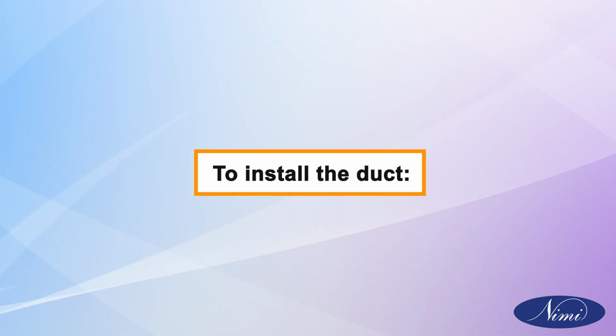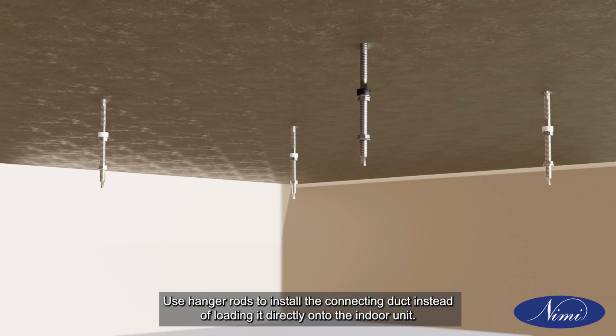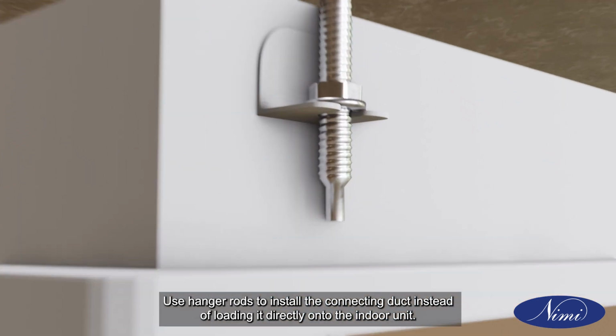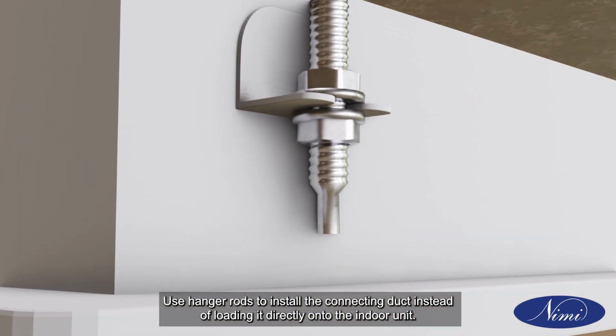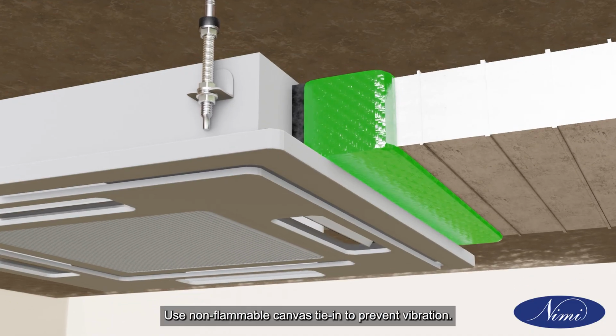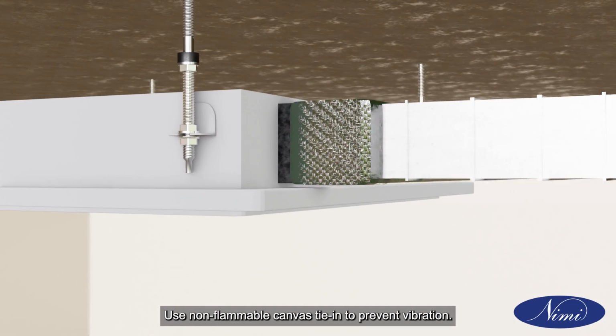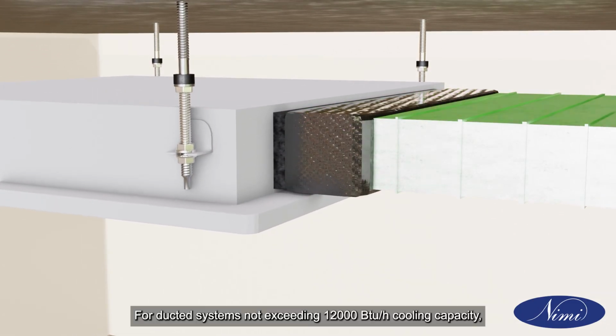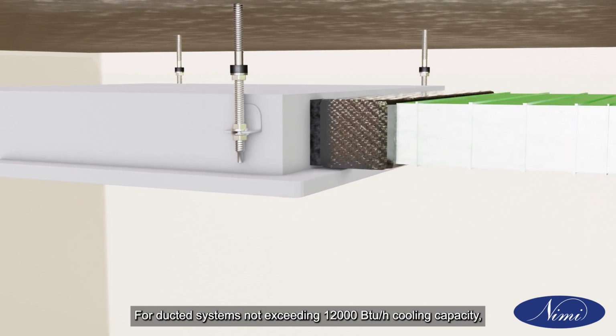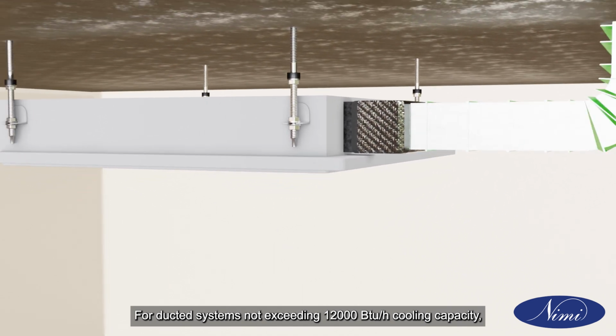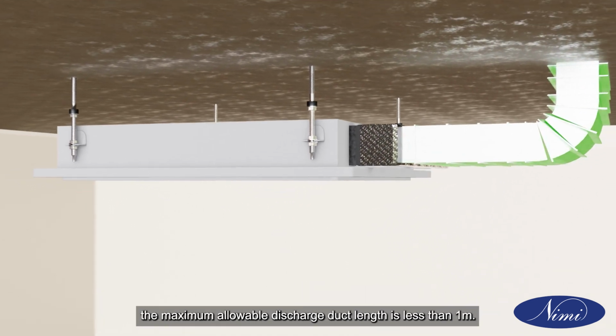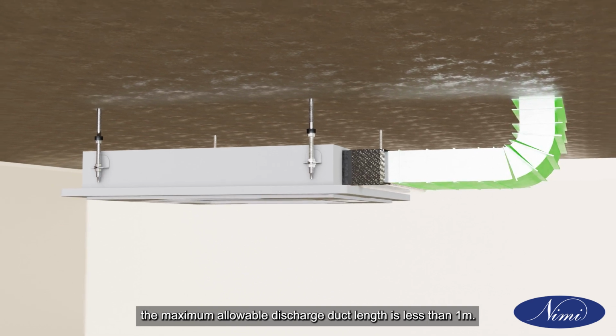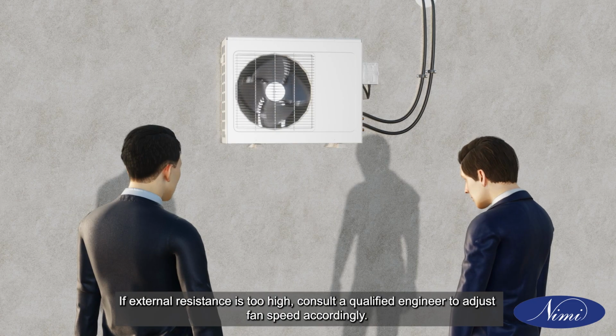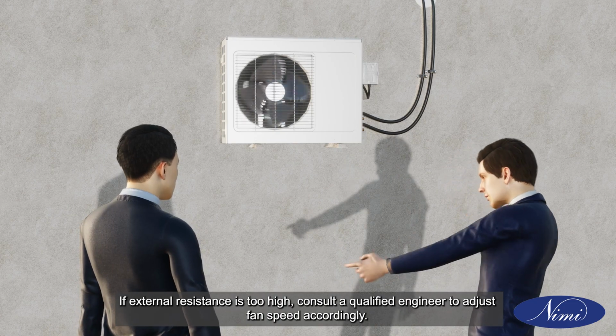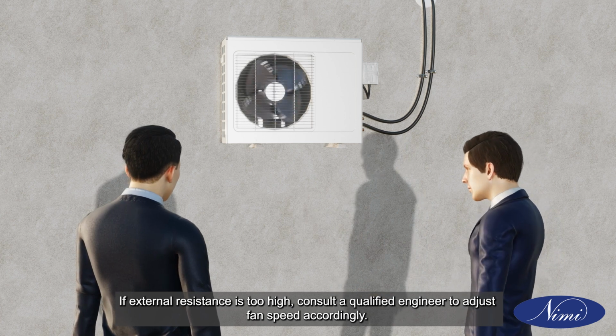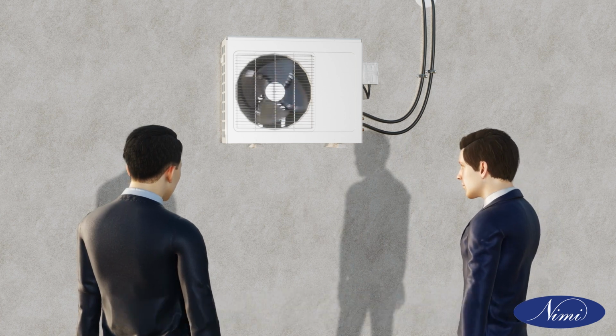To install the duct, use hanger rods to install the connecting duct instead of loading it directly onto the indoor unit. Use non-flammable canvas tie-in to prevent vibration. For ducted systems not exceeding 12,000 British thermal units per hour cooling capacity, the maximum allowable discharge duct length is less than 1 meter. If external resistance is too high, consult a qualified engineer to adjust fan speed accordingly.